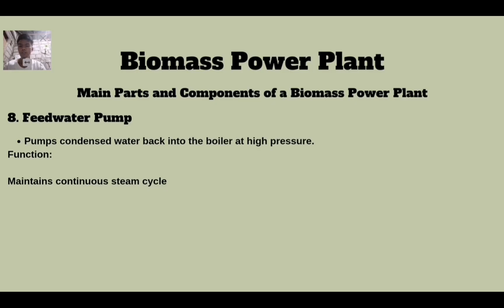Number 8 is the feed water pump. It pumps condensed water back into the boiler at high pressure, maintaining continuous steam cycles.